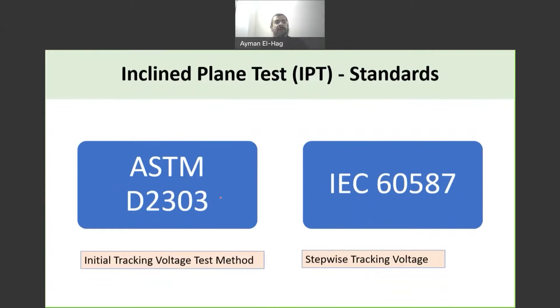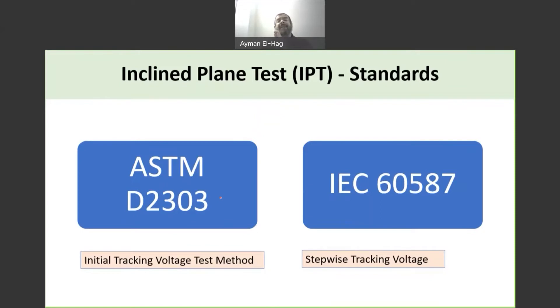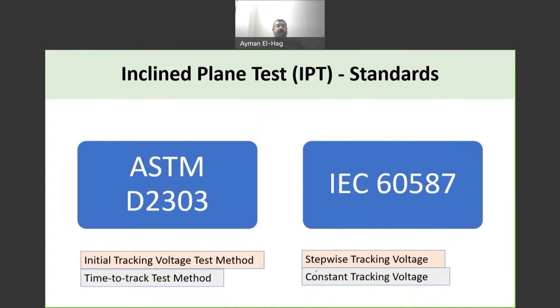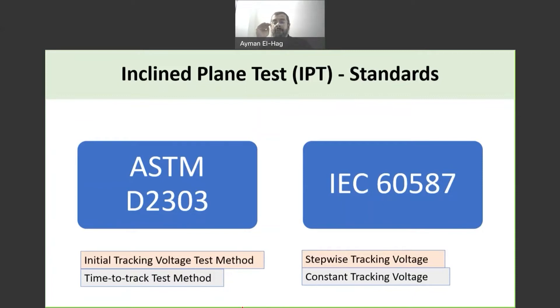The first method is called the initial tracking voltage test method and the second is the stepwise tracking voltage. In these two methods, we apply a voltage and keep increasing it by 250 volts until the material fails — hence the name stepwise tracking voltage. But the most common method, which I personally prefer and which the industry uses more, is the time-to-track test as named by ASTM, or the constant tracking voltage. In this method, we apply a certain voltage and keep the material under test for six hours to see whether the material passes or not.